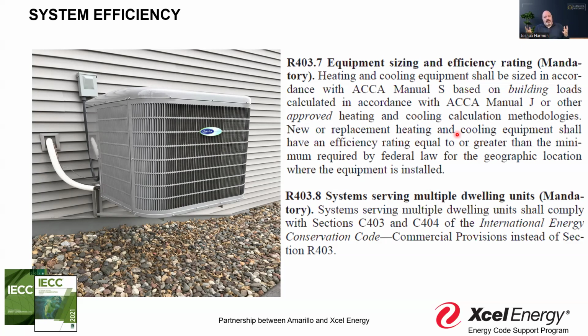That comes straight out of whether we're getting it from 1505 in the IRC, or section 3 of the IMC, or section 4 for the UMC. What we're expecting is that they've calculated a design based on occupancy size, level of occupancy, level of activity, and the thermal envelope design - how much latent and sensible heat load are we going to get from this potential project. They make that calculation to say this is the right piece of equipment.